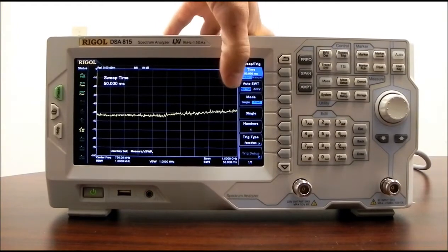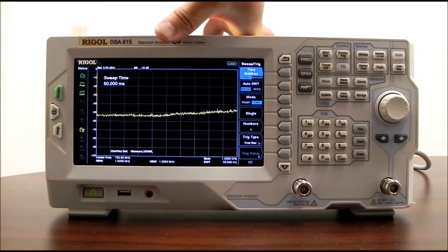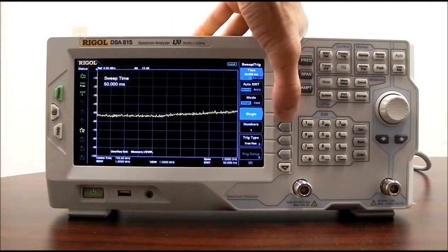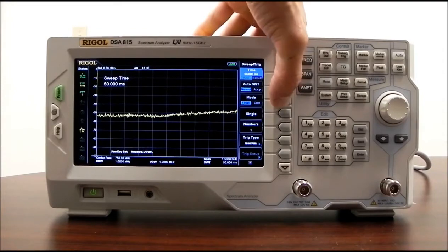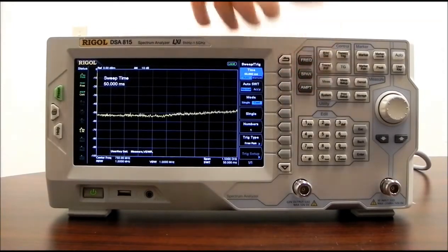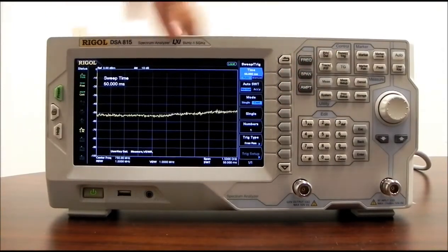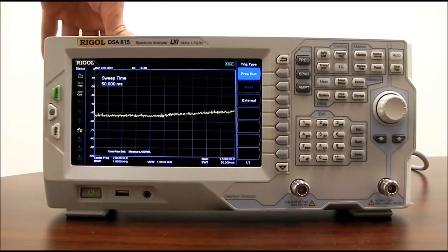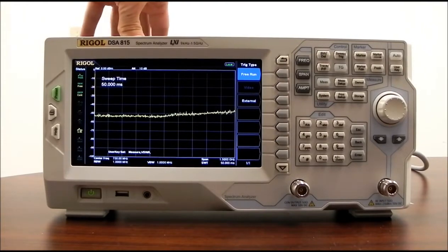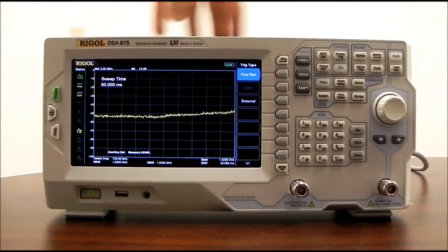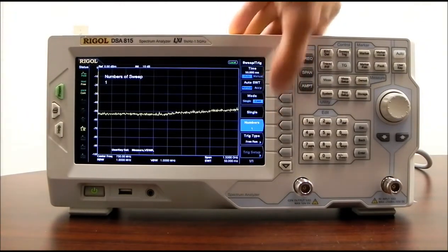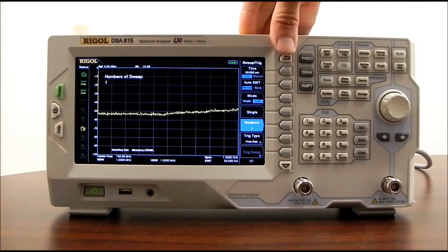We have auto sweep time. We want to keep that normal, or we can go to accuracy mode. Then for mode, we can go continuous or single, and with single we can just press single trigger if we wanted to capture just one image. We also have the ability to do an internal trigger, which is free run, but we can also do external. There is a BNC connector on the back, a TTL level signal, so if you wanted to trigger it in an automated way in order to capture images, you could do that as well. You can set the number of scans per trigger using the numbers key.